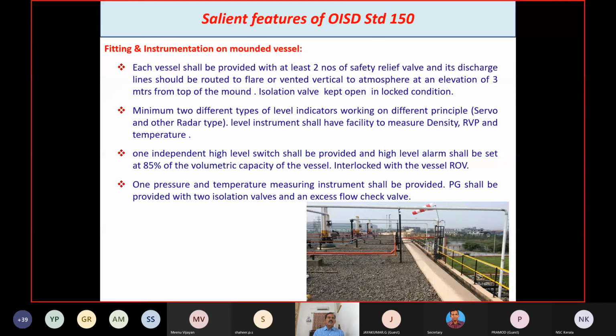And one independent high level switch shall be provided, and high level alarm shall be set at 80% of the volumetric capacity of the vessel, because it should not be filled completely, and 15% should be left for expansion and vapor space. And the ROV should be interlocked, and the interlock system should be ensured. If the level reaches high level, it should have interlock with the ROV. The inlet ROV of the vessel should close automatically. One pressure and temperature measuring instrument shall be provided, and the pressure gauge shall be provided with 2 isolation valves and an excess flow check valve.